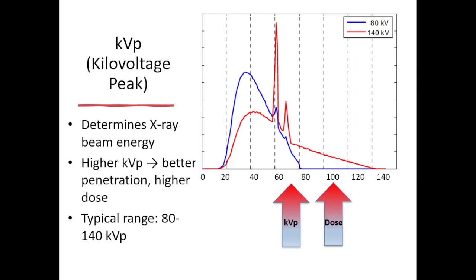Typically, 80 kVP is used for pediatric scans and adult head scans, while 120 kVP is widely used for adult body scans. It's important to note that x-ray tubes generate a spectrum of x-ray energies. When we say 140 kVP, this refers to the peak energy, but the mean energy is usually about one-third of the peak value. Here is an example of the energy spectrum for a 140 kVP and an 80 kVP spectrum, where 80 and 140 refer to the peak energy.